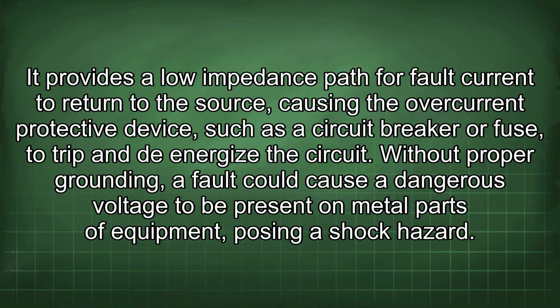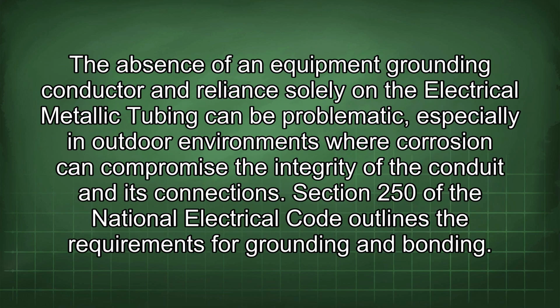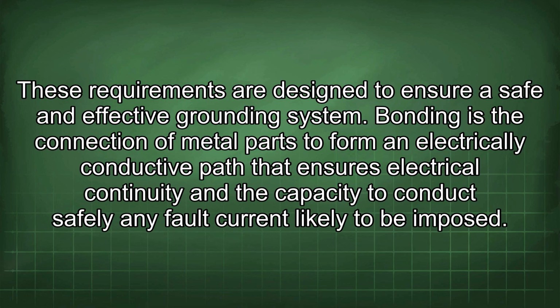Without proper grounding, a fault could cause a dangerous voltage to be present on metal parts of equipment, posing a shock hazard. The absence of an equipment grounding conductor and reliance solely on the electrical metallic tubing can be problematic, especially in outdoor environments where corrosion can compromise the integrity of the conduit and its connections. Section 250 of the National Electrical Code outlines the requirements for grounding and bonding. These requirements are designed to ensure a safe and effective grounding system.